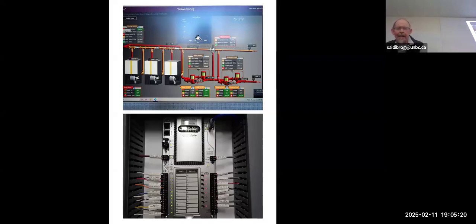There's a line going here - this is the outside temperature, and this is the boiler water temperature. So it follows automatically this scheduling, depending on outside air temperature, as to what the secondary water is going to be run at. This is one of the controllers that controls these systems - there's about 10 of them in the building.